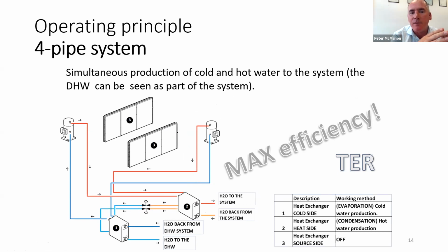there are so many applications. There's a lot of applications where you have a simultaneous requirement for heating and cooling. And as I explained earlier, there's no point having a chiller doing the cooling, dumping the energy, and you're generating heat elsewhere when we can recover that energy. So that's really what the multifunctional heat pump is all about.